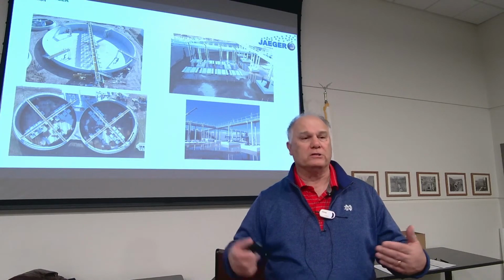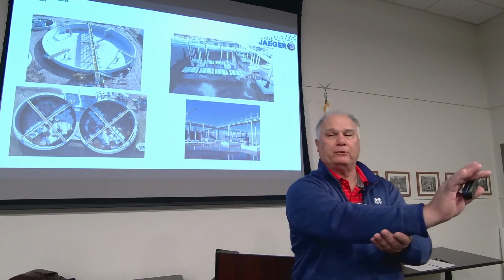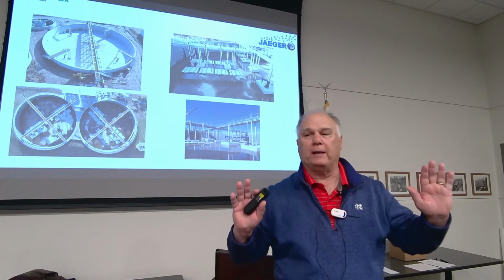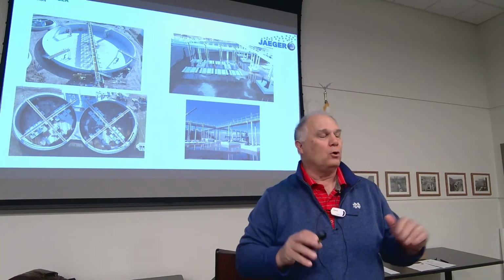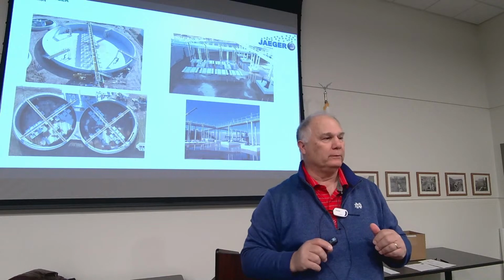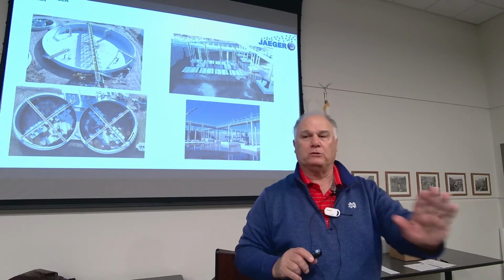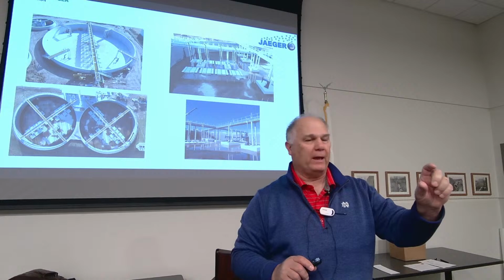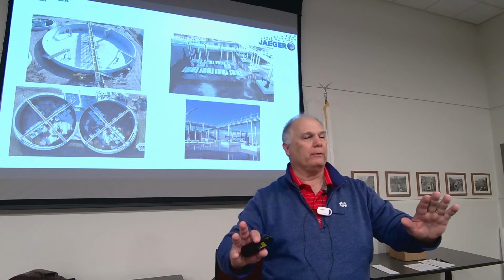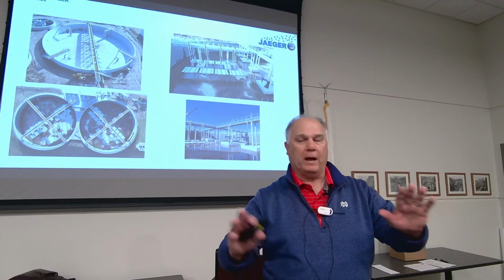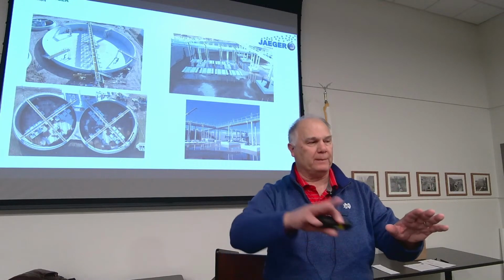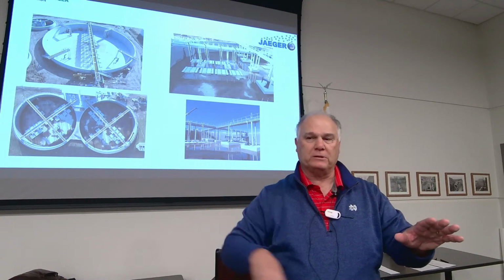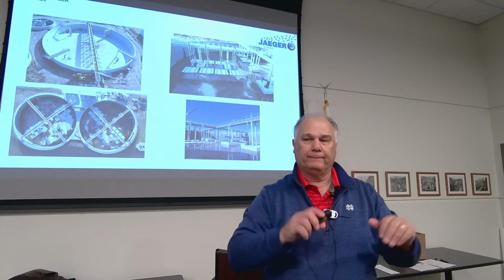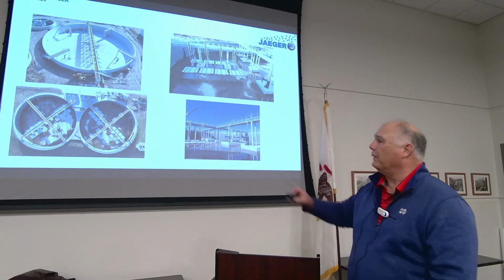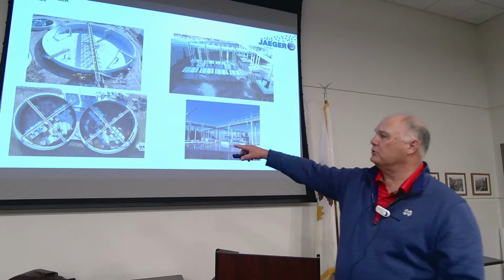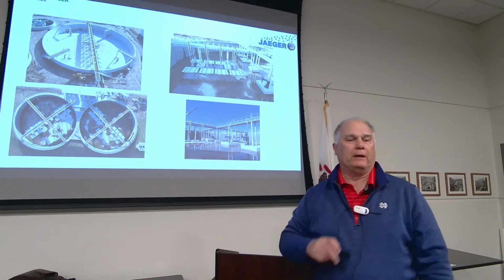Because our goal is to push this water across that membrane diffuser and keep those bubbles all individual bubbles. We don't want them to accumulate together. And therefore, when we have the aerobic time, we're blowing air into those diffusers. In anoxic time, we're not blowing any air, we're still mixing that basin. We're mixing that basin even in the anaerobic time. But we can go into any tank, dimension, style, whatever, and retrofit it.